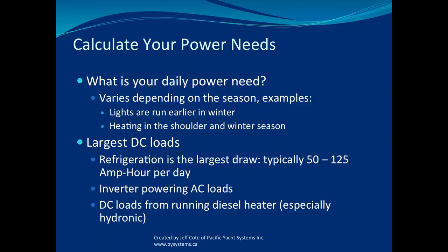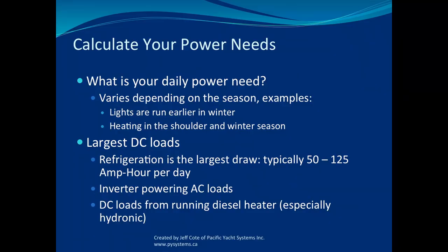When sizing a battery bank, you've got to ask yourself: what are your daily amp hour requirements? People come to me and say, 'I need a battery bank, Jeff. How much?' And I say let's go down the rabbit hole together — it's like asking how much to remodel a kitchen. There's not a single solution for every one of us. The first thing you've got to figure out is your daily amp hour requirements. You cannot size a battery bank without knowing what you need — it's like sizing your retirement without knowing your burn rate.